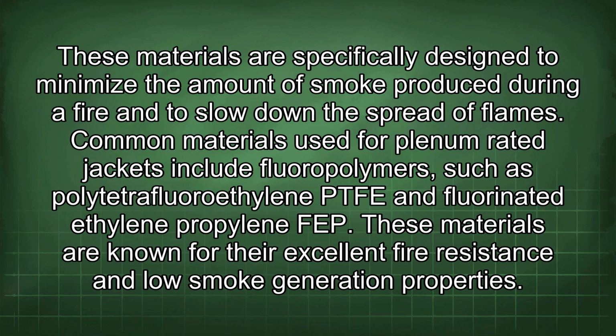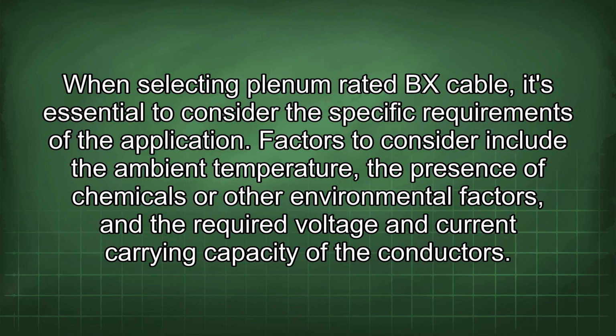Common materials used for plenum-rated jackets include fluoropolymers, such as polytetrafluoroethylene (PTFE) and fluorinated ethylene propylene (FEP). These materials are known for their excellent fire resistance and low smoke generation properties. When selecting Plenum-rated BX cable, it's essential to consider the specific requirements of the application. Factors to consider include the ambient temperature, the presence of chemicals or other environmental factors, and the required voltage and current carrying capacity of the conductors.